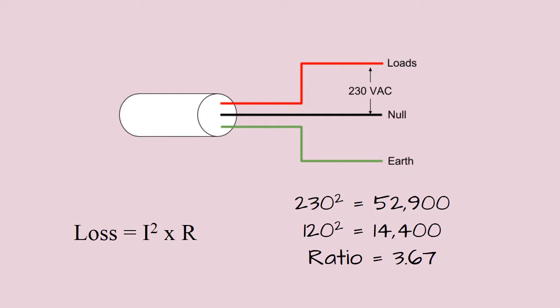There are advantages to using 230 volts compared to 120, and it is related to loss in the cable. The losses in the cable is I squared times R. If we assume that the cable resistances are the same, then 230 squared is 52,900 and 120 squared is 14,000. The losses in the 120 volt system are over 3.5 times.